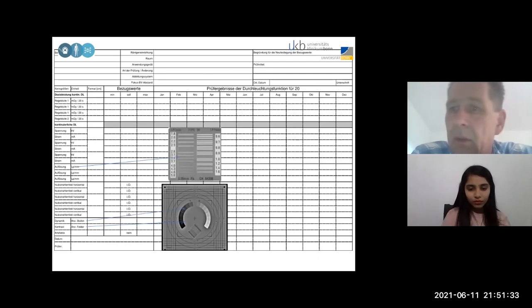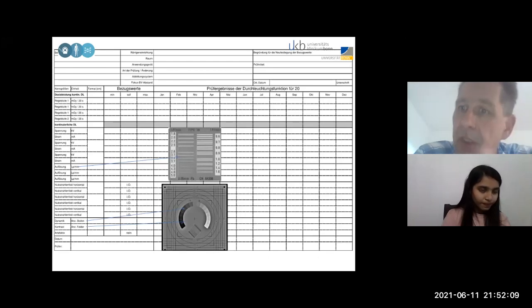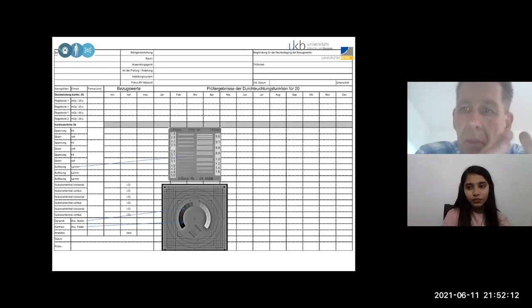This should be done monthly. So check the energy, as the dose, for certain field sizes. Check the voltage and the current for certain field sizes. Check the resolution. Check whether your field at 90 degrees and at 0 degrees is the same; you see, gravity could be a problem. Then you should count the steps. You should see the contrast and look for artifacts. That is what we do for a conventional X-ray machine on a monthly basis.